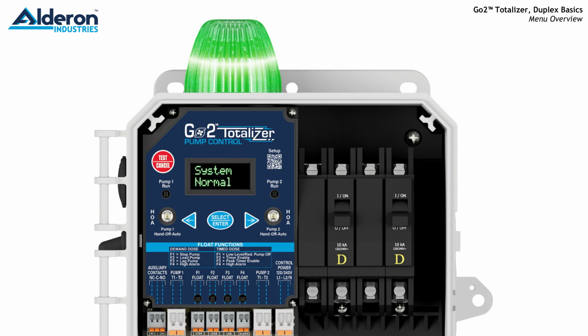Out of the box, the Go2 Totalizer Duplex is configured for a demand pumping system utilizing 4 float switches: off, lead, lag, and high-level alarm. No further settings are required. Simply connect the floats, pumps, and power to the proper terminals, and you are finished.